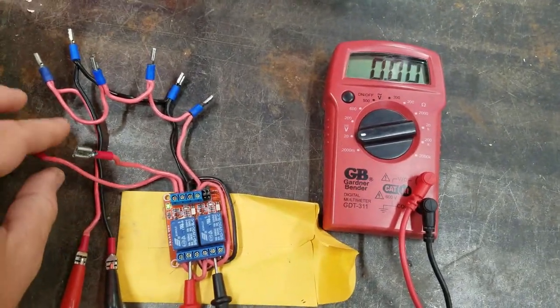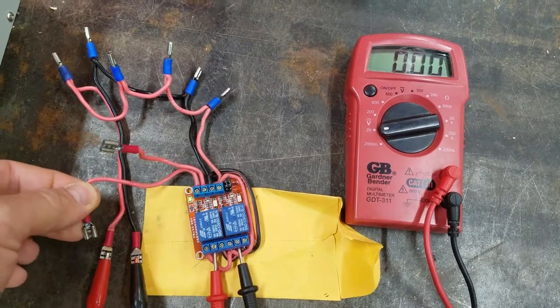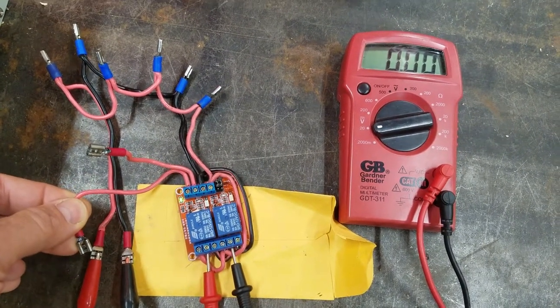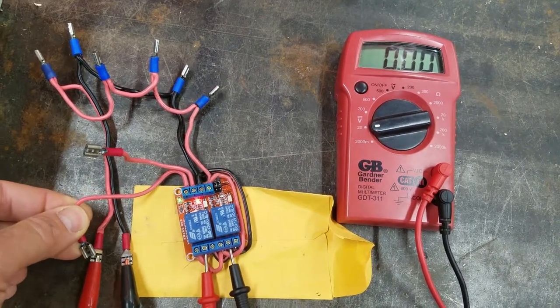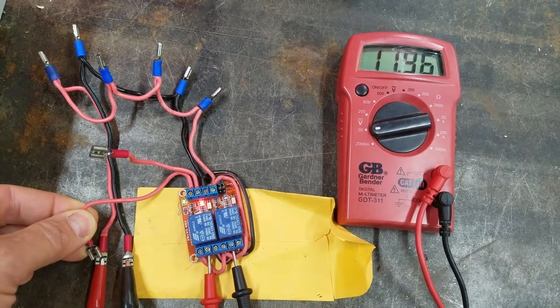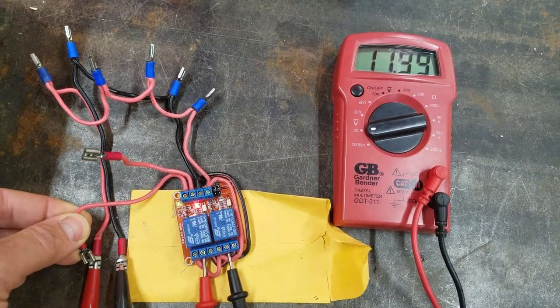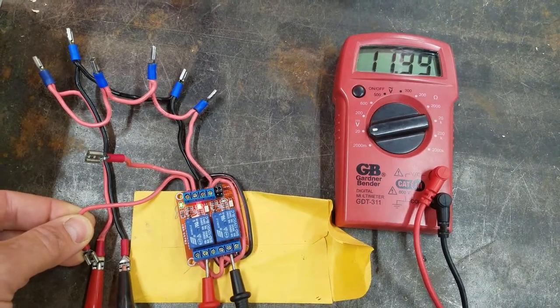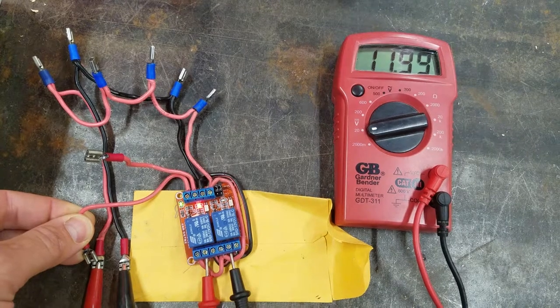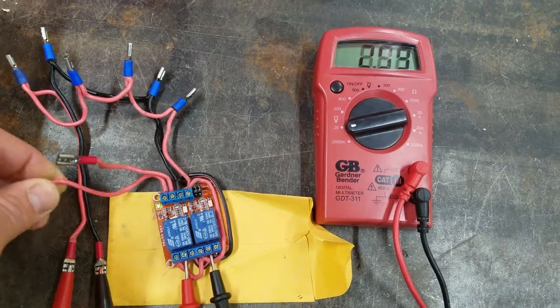To trigger it manually, all you do is take the signal wire—this is the IN1 wire—and I'm just going to touch it to positive power. The red light goes on, it shows 12 volts, and that means the relay is functioning fine.